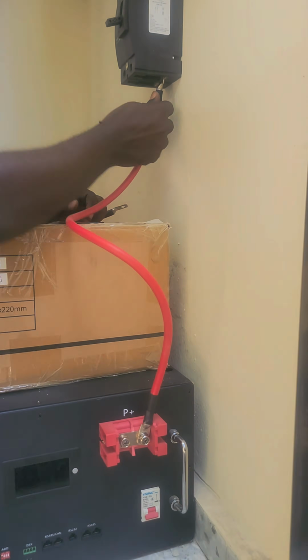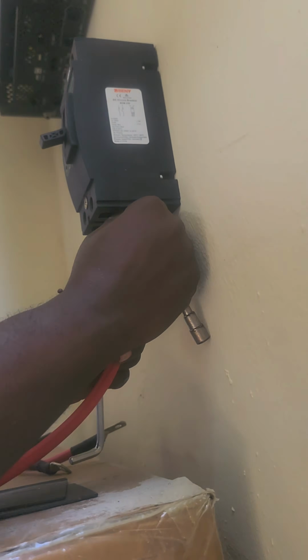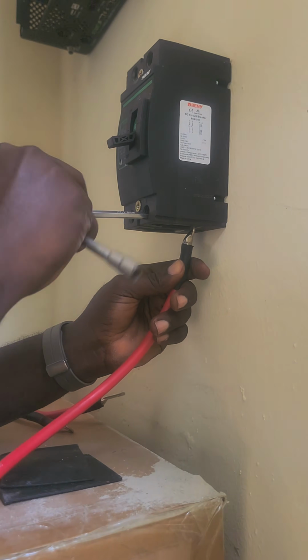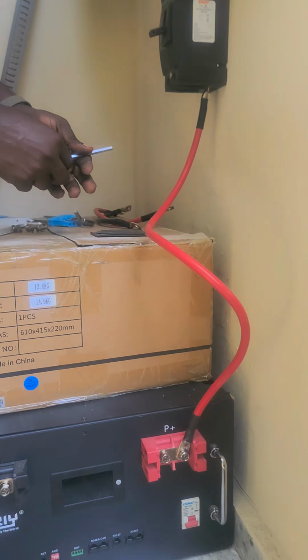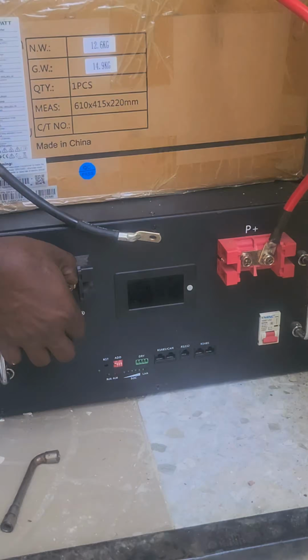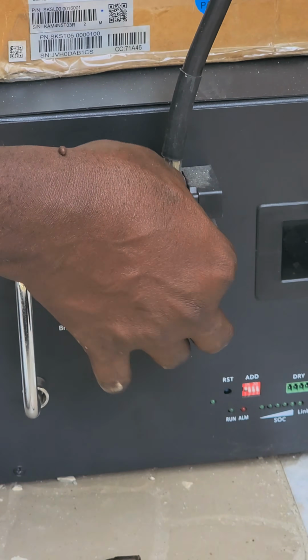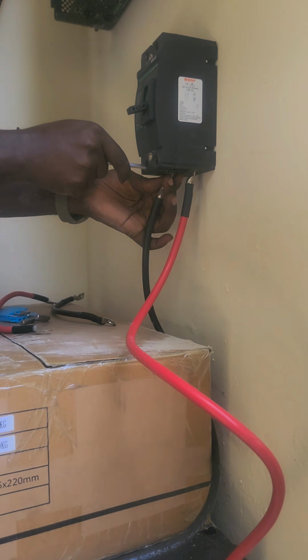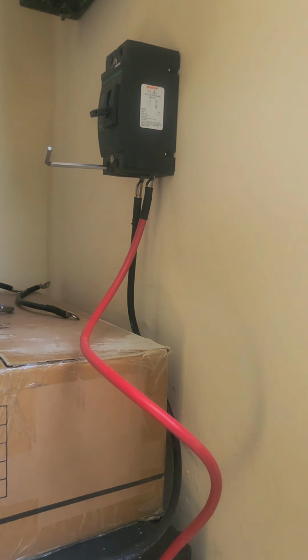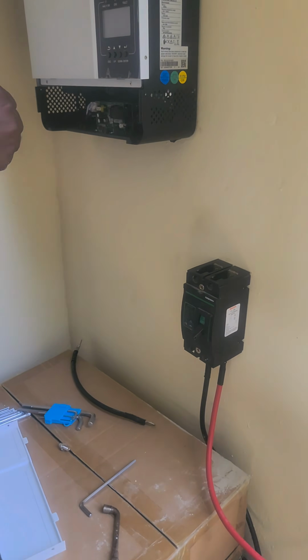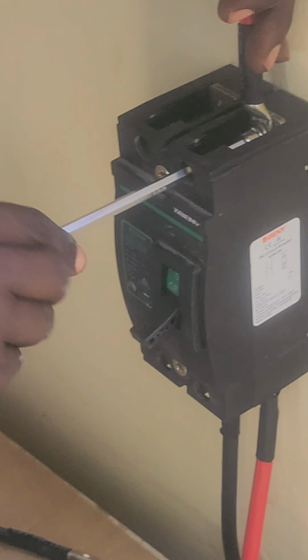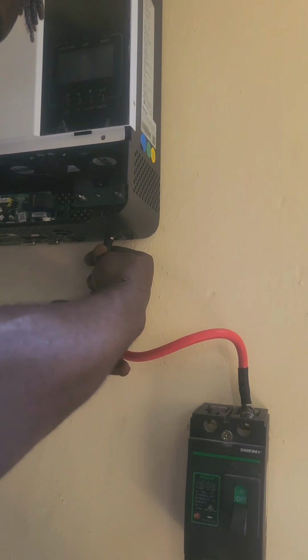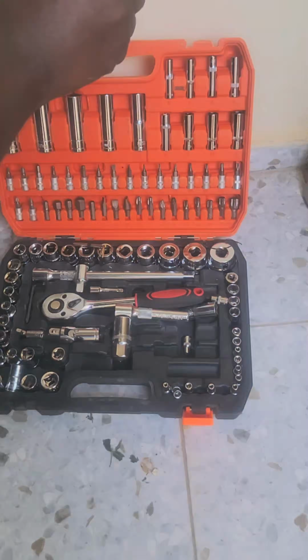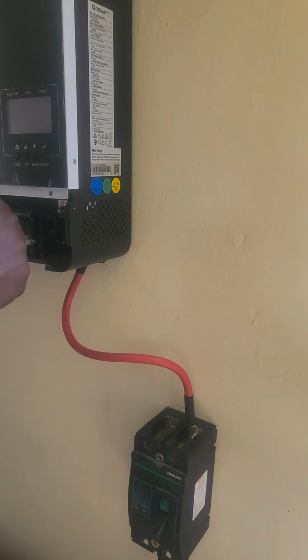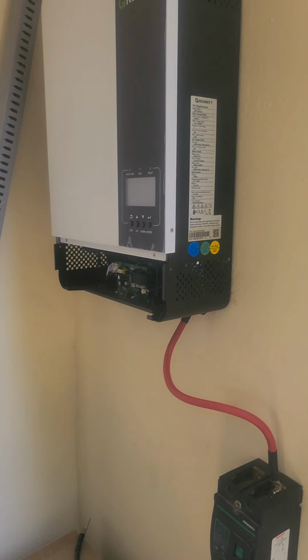So now I'm connecting the battery to the MCCB. As I was saying, the MCCB is really what you want to use. It's much bigger and more capable than the smaller MCB we use for the combiner box. They're ideal for high current applications. Anything above 125 amps, you want to use an MCCB. The good thing again is that the MCCB protects both ways. So if the bad current is coming from the inverter, it will protect the battery. If the bad current is coming from the battery, it also protects the inverter. So it works both ways, and it allows for a disconnect between the battery and the inverter.